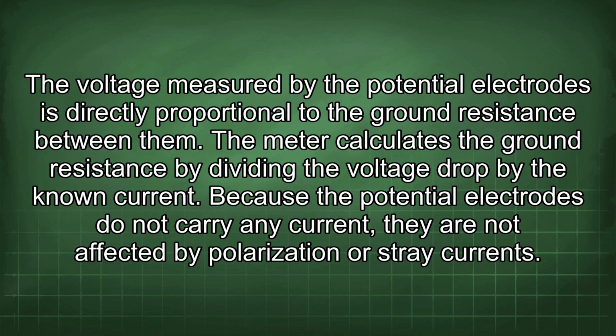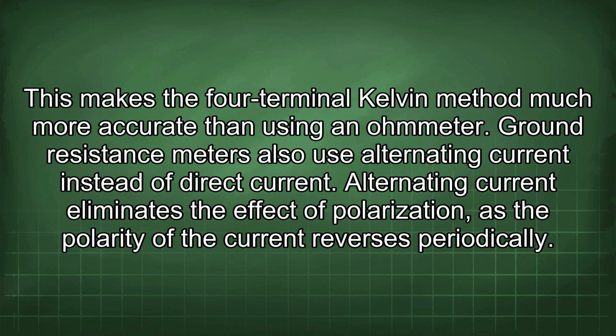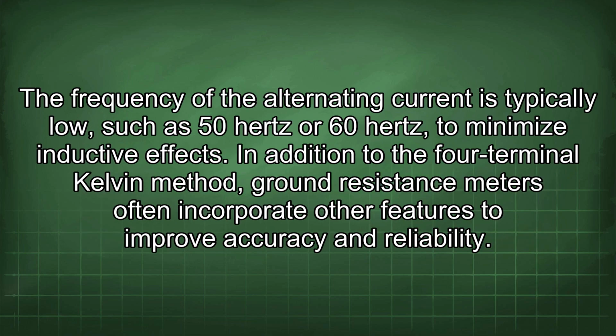Because the potential electrodes do not carry any current, they are not affected by polarization or stray currents. This makes the 4-terminal Kelvin method much more accurate than using an ohmmeter. Ground resistance meters also use alternating current instead of direct current. Alternating current eliminates the effect of polarization as the polarity of the current reverses periodically. The frequency of the alternating current is typically low, such as 50 Hz or 60 Hz, to minimize inductive effects.